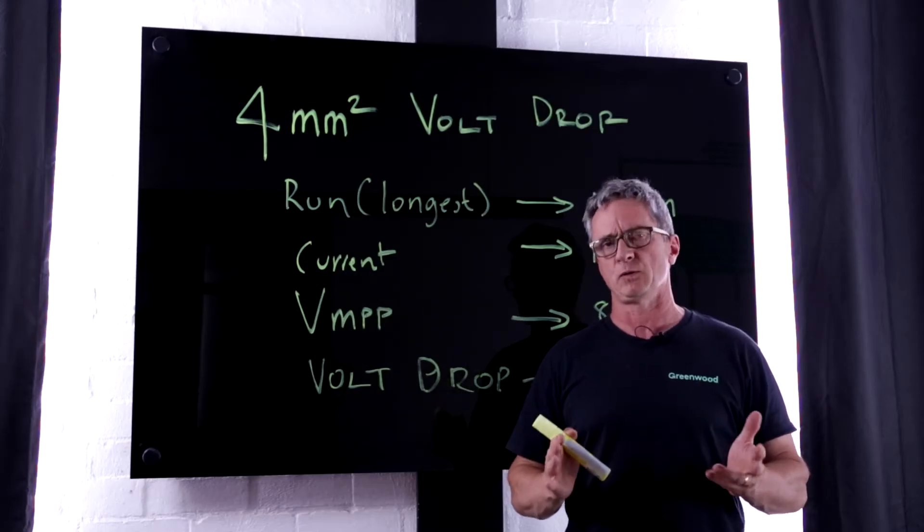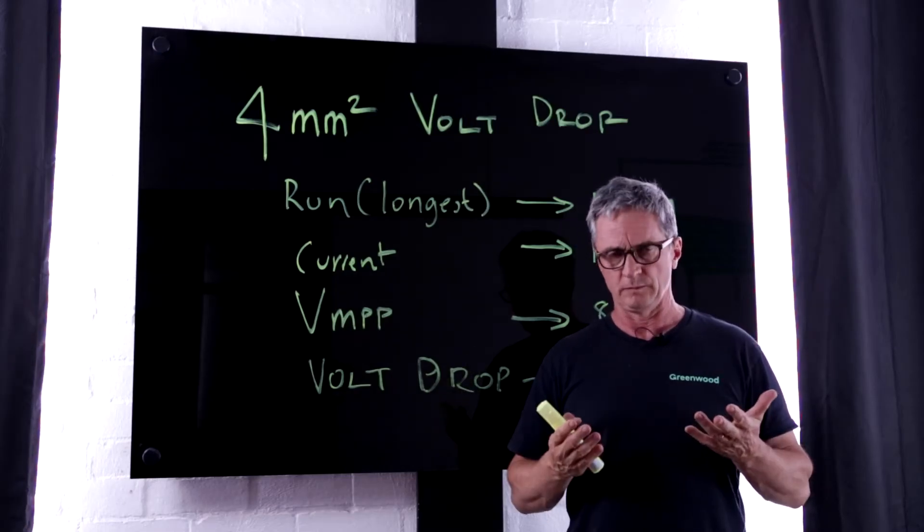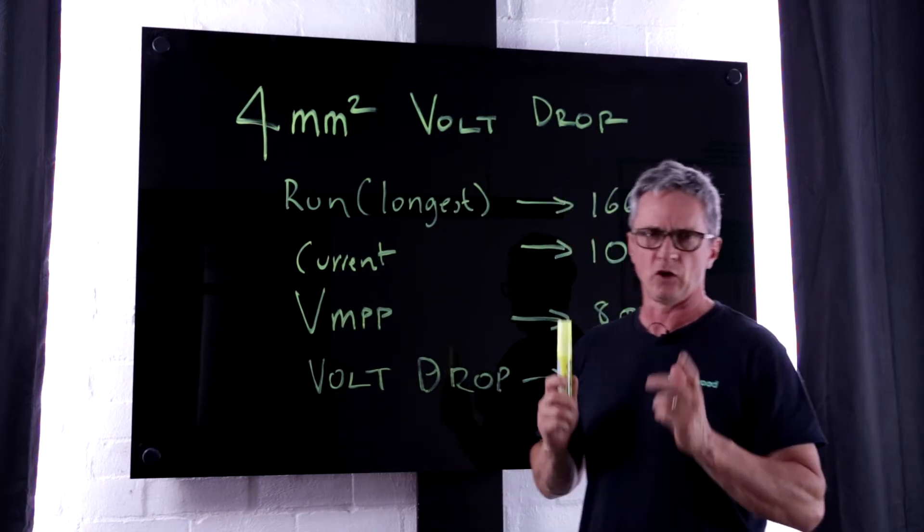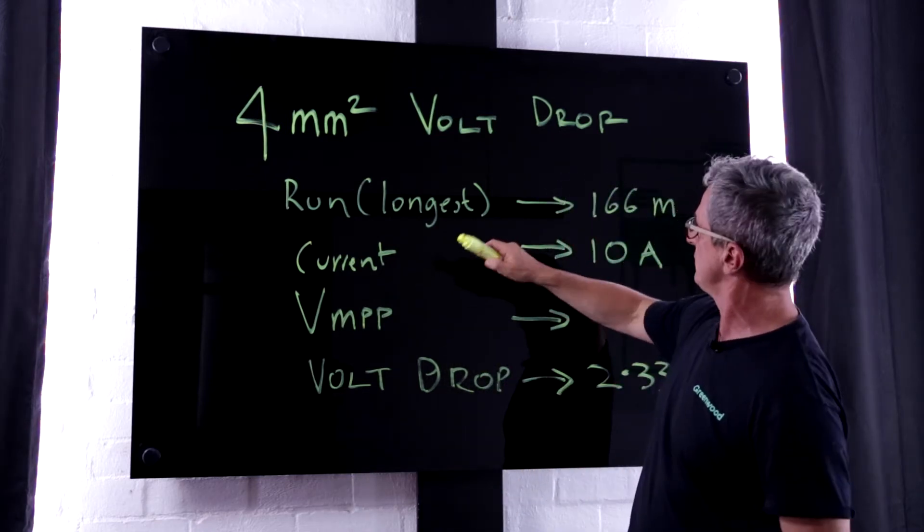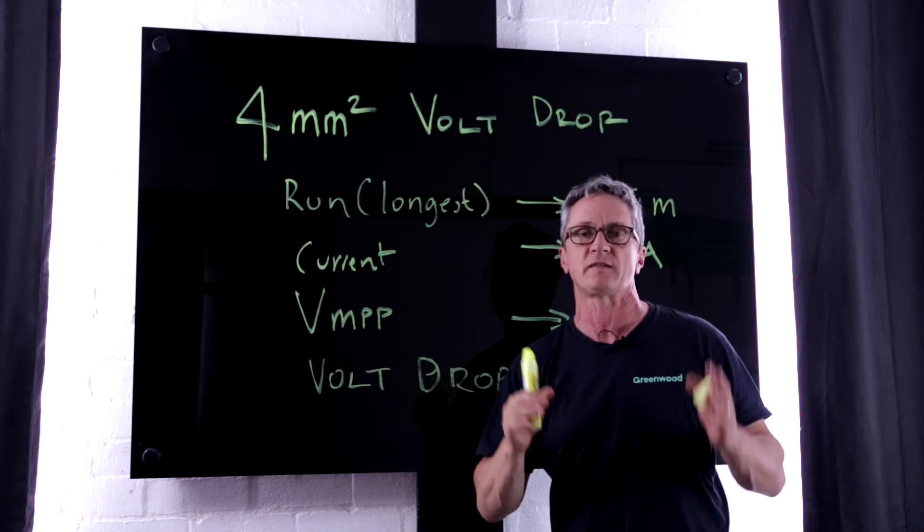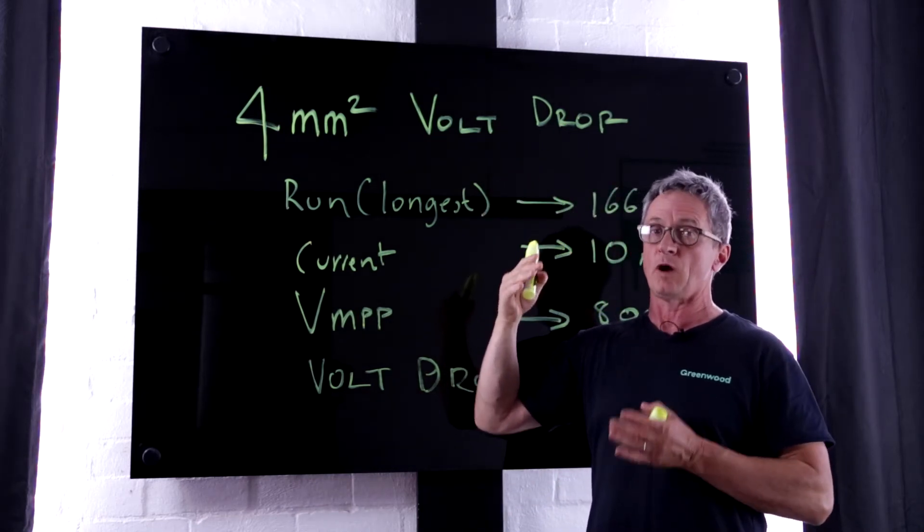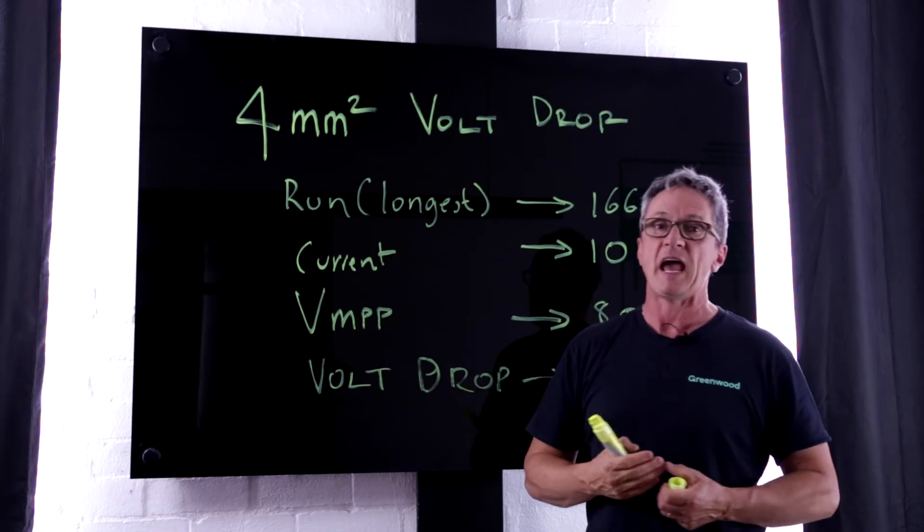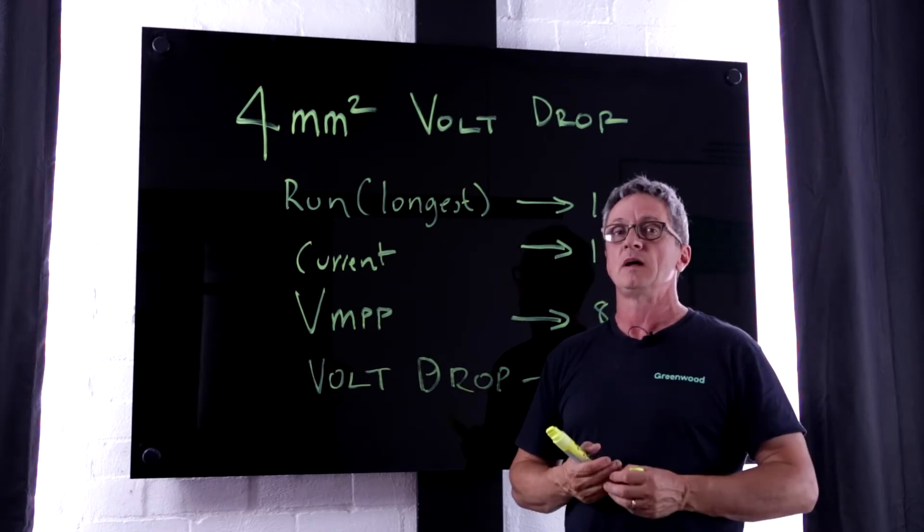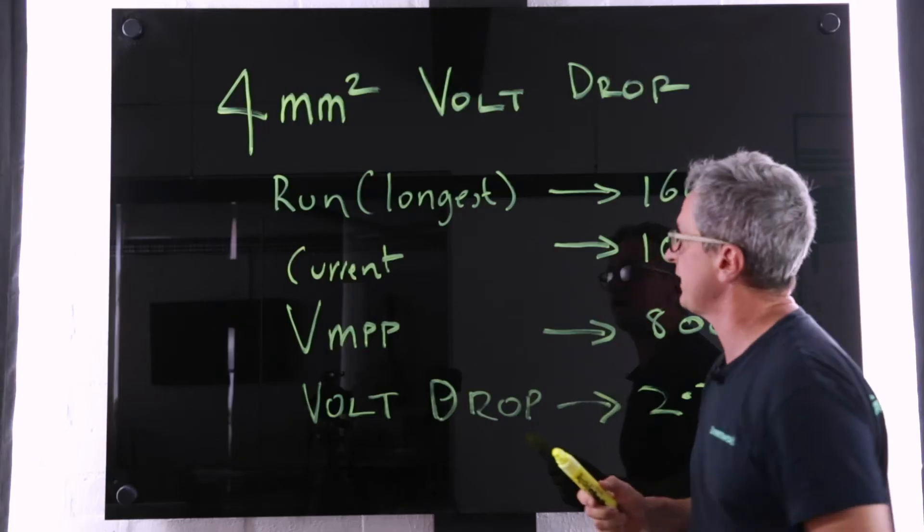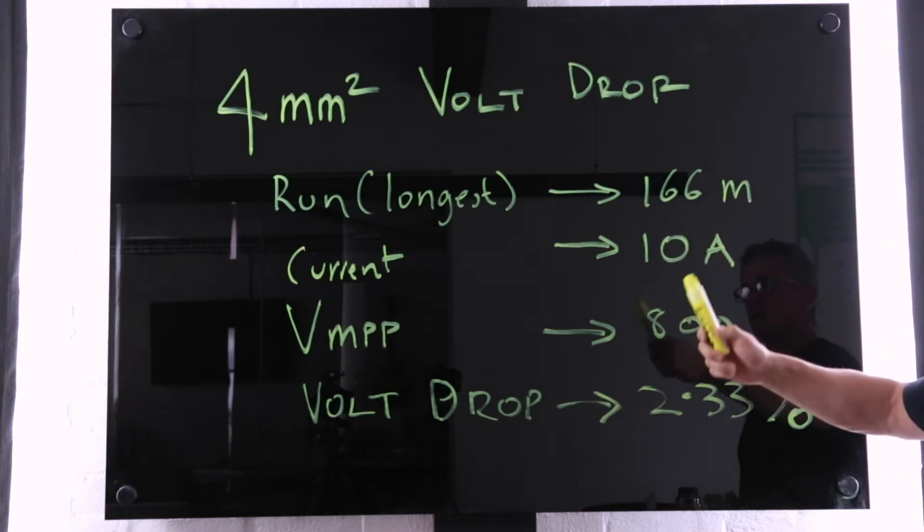We're talking 4mm cable, single, non-paralleled runs. Now the longest run obviously is 166 meters and that's made up by the 133 meter run between row number 1 and row number 20 and then add on another 30 odd meters. So that's the calculation we're doing on our volt drop calculation.